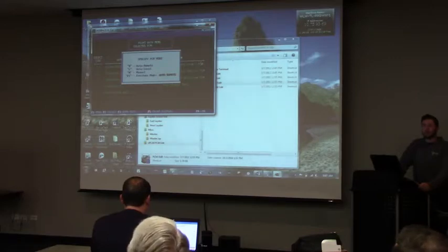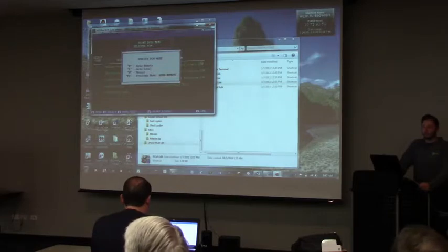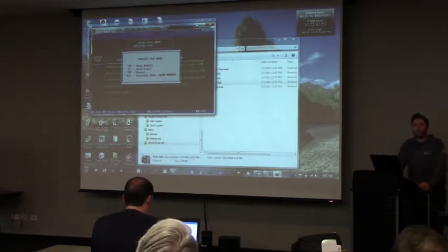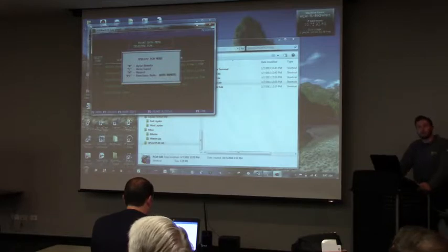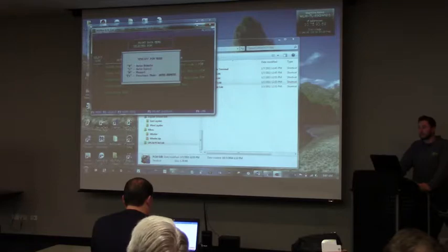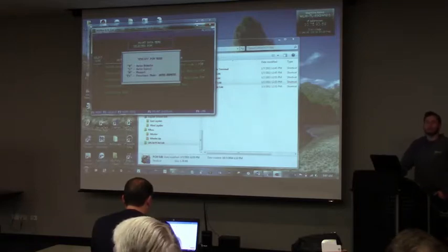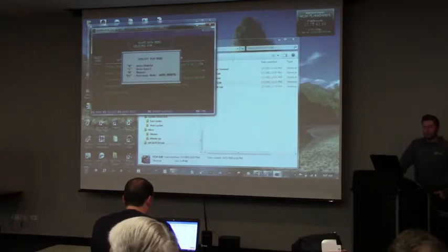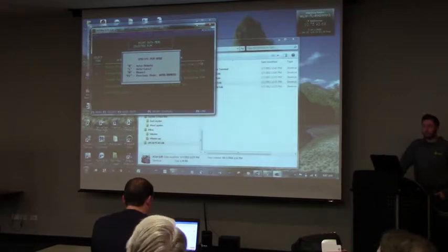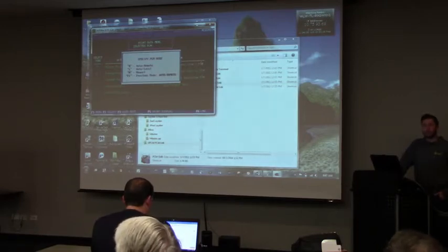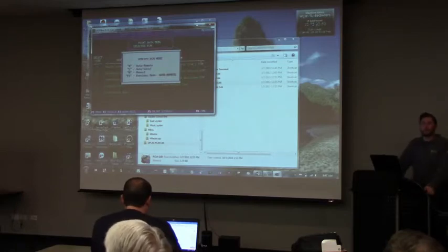Where that really burns you is if you're working with a heating or cooling plant and it's winter timeout and it's running in a winter mode, or let's say it's summer timeout, it's running in a summer mode. If you put it in auto local, chances are good the default value for winter summer mode is always winter mode because you want to fail for heat. So then you wonder why the chiller shut off and all this other stuff happened.